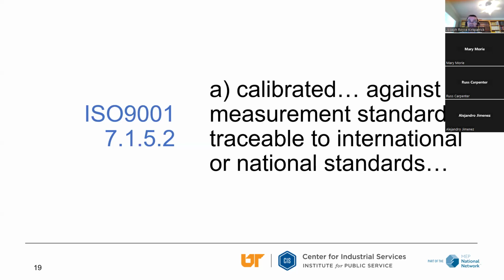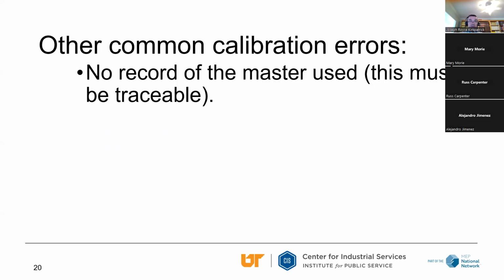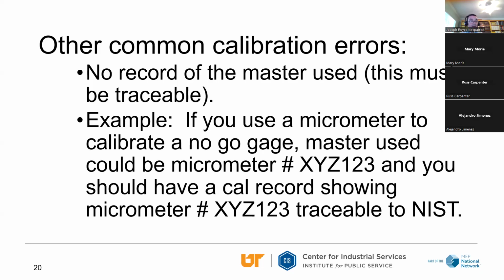ISO says you've got to calibrate gauges against a measurement standard that's traceable to some kind of international or national standard. Other common calibration errors: not recording the master used. And the master must be traceable to a national or international standard. In the US, it's typically NIST, the National Institute of Standards and Technology. An example, if you're using a micrometer to calibrate a go, no-go gauge, and it's okay to do that, the master used might be micrometer number XYZ123, and you should have a calibration record for that micrometer that's traceable to NIST. And the calibration record of the go, no-go gauge needs to reference that you used this micrometer. This was the master that was used. If you don't reference that, you've lost the link to your NIST traceability. And that's a common error in calibration records. You always must include the traceability of the master used, and that master needs to be traceable to NIST.